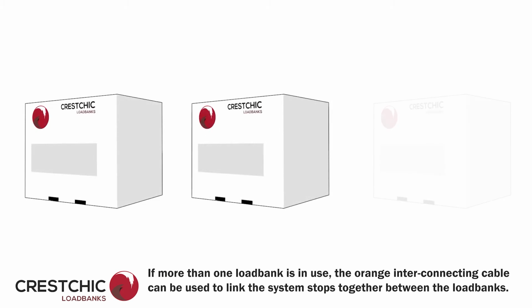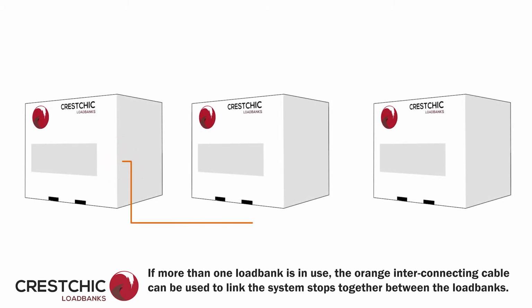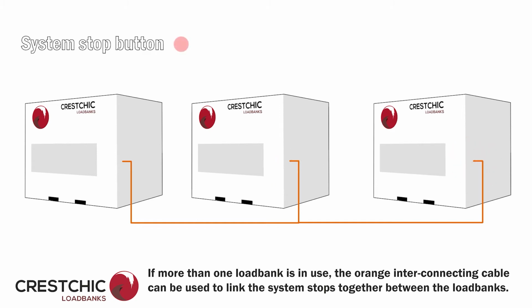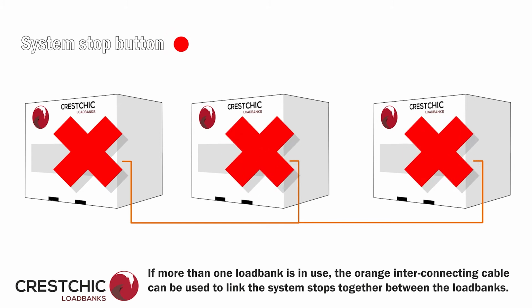It is possible to link the system stops when having more than one load bank. This is done using the orange interconnecting cable. Once connected, pressing the system stop on one load bank will activate the system stop function on other load banks connected.